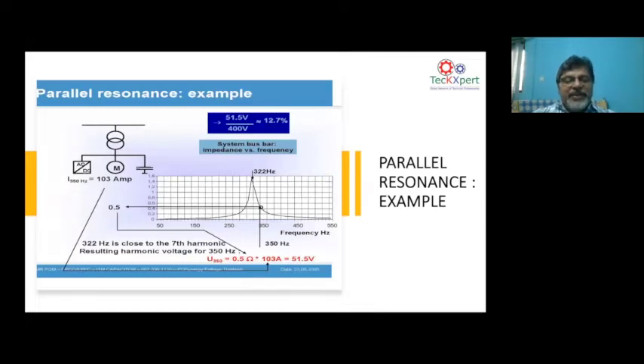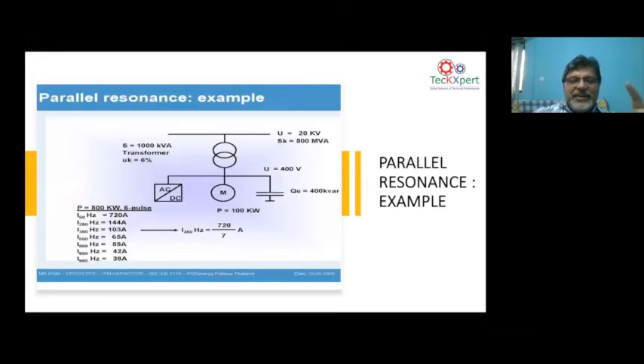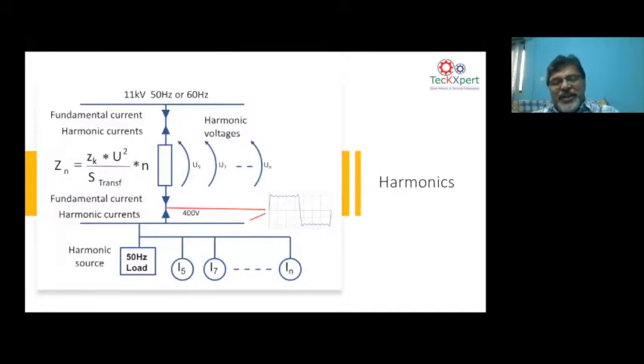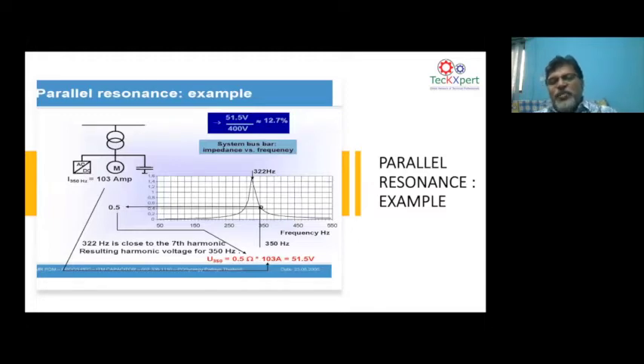So once you know the network impedance corresponding to the 7th harmonic, and if you know the 7th harmonic current is 103 amps, then you calculate the ohmic value of it, and then you come to the actual percentage. Now you can see, if you go back to the previous slides, there's a 1000 kVA transformer, and there is a 400 kVA capacitor bank. As you go forward, you will see the 7th harmonic frequency is getting amplified, and you are getting 12.7% harmonic voltage distortion by the 7th harmonic. That means when you add a 400 kVA capacitor bank on a 1000 kVA transformer, you are creating a resonant frequency near to the 7th harmonic, and in turn you are creating a 7th harmonic voltage of 12.7%, which is around 51.5 volt. So this is the way to explain a parallel resonance when you add a capacitor bank into the network. Go to the next one.